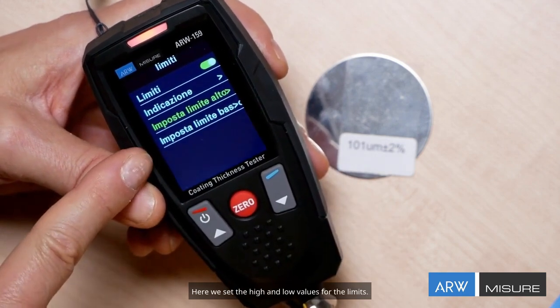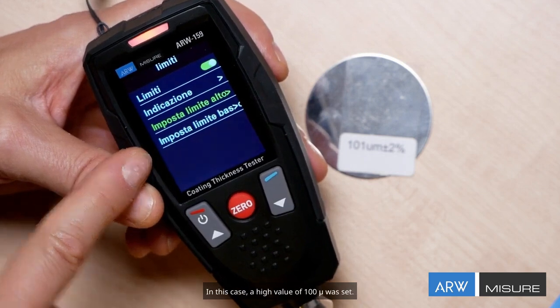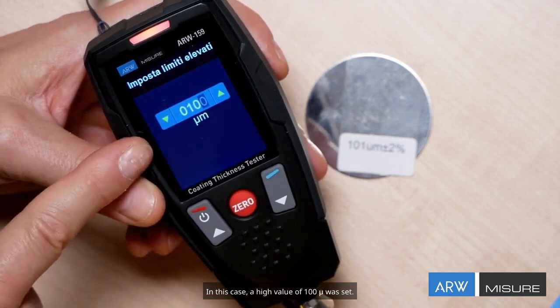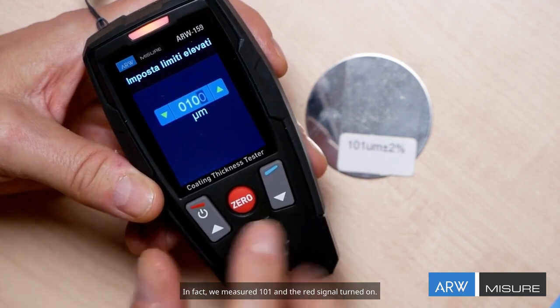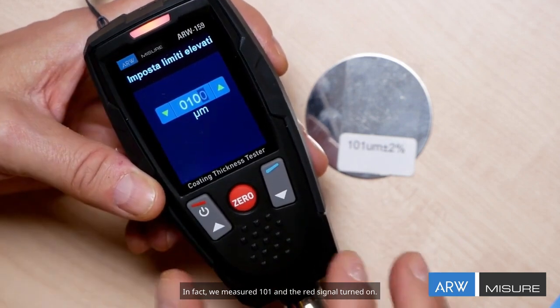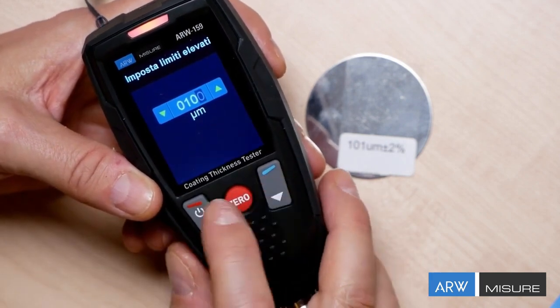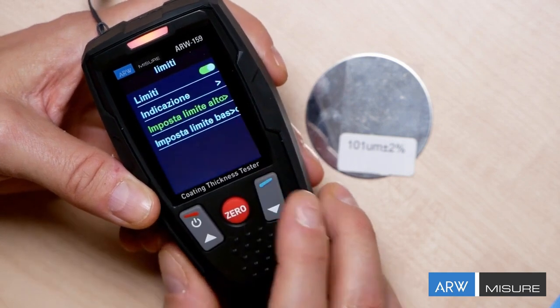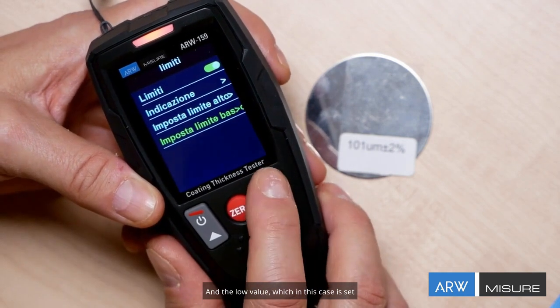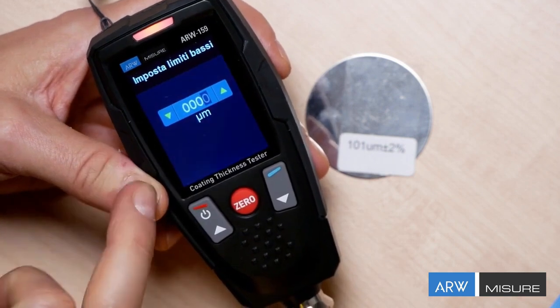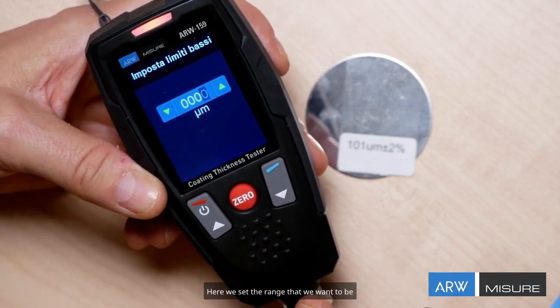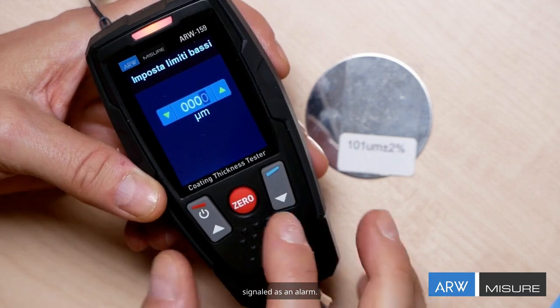Here, we set the high and low values for the limits. In this case, a high value of 100 µm was set. In fact, we measured 101 and the red signal turned on. And the low value, which in this case is set to 0. Here, we set the range that we want to be signaled as an alarm.